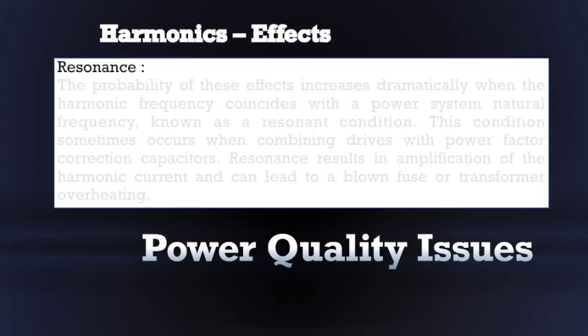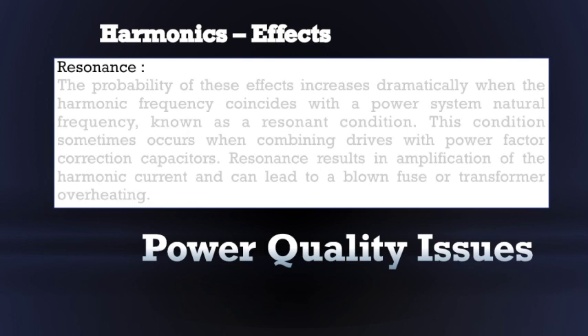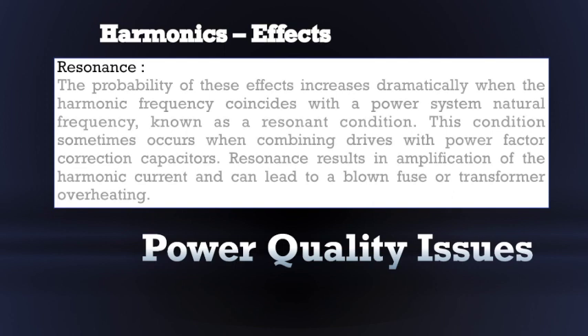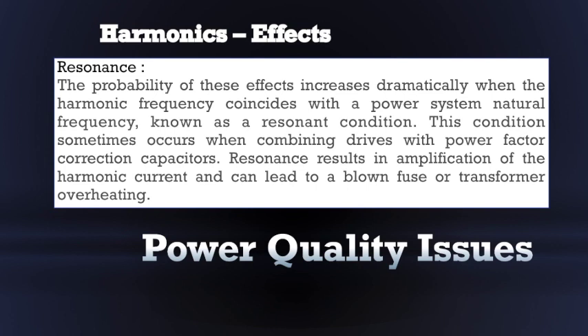Now we will see resonance. When the harmonic frequency coincides with a power system natural frequency, resonance occurs. This condition sometimes occurs when combining drives with power factor correction capacitors. Resonance results in the amplification of the harmonic current and can lead to blown fuse or transformer overheating. After all, the negative impact of harmonics may not be immediately evident, but over time can result in increased power demand, system loss, and shorter equipment lifetimes.